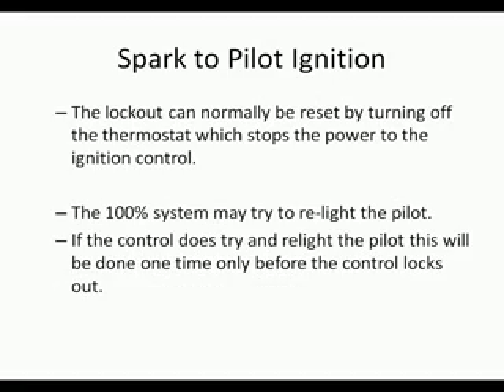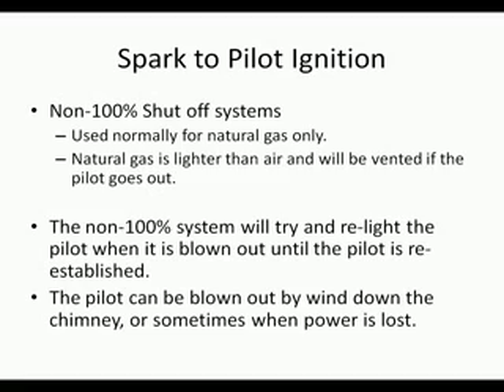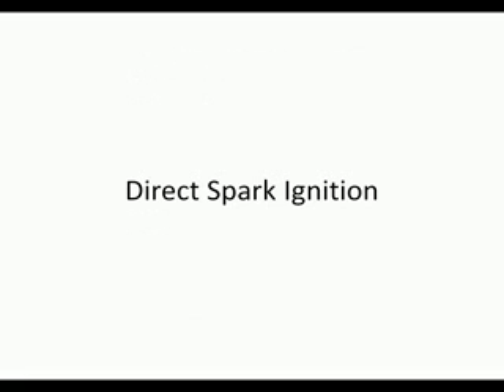There are two types of spark ignition systems: the 100% shutoff and the non-100% shutoffs. The 100% shutoffs mean that if there's a fault or if something happens during the ignition process or during the burn, the system will lock out the burner after approximately 45 seconds. It's normally used for propane systems, as propane is heavier than air and will pool on the ground. The lockout can normally be reset by turning off the thermostat, which stops the power to the ignition control. The 100% systems may try to relight the pilot once. If the control does try to relight the pilot, this will be done one time only before the control locks out. Again, it's a safety to make sure unburnt gas doesn't pool around the furnace.